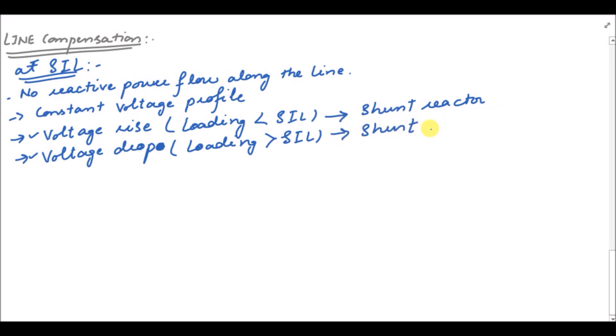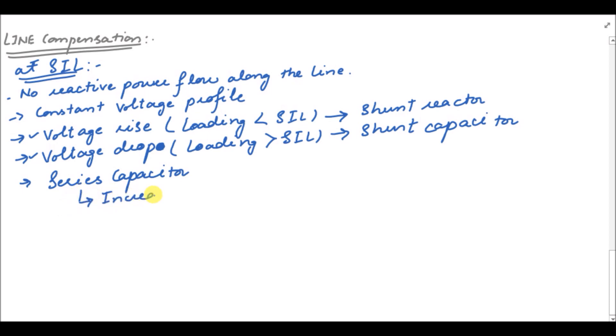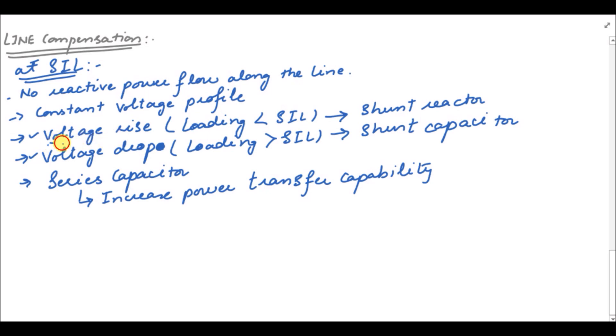In the case of voltage drop we use a shunt capacitor. There is another case in which we use a series capacitor at approximately the mid-point of the transmission line, to increase the power transfer capability of the line. In today's lecture we are going to talk about the first part, which is the addition of a shunt reactor in the transmission line whenever we have a voltage rise condition at the end of the unloaded transmission line.